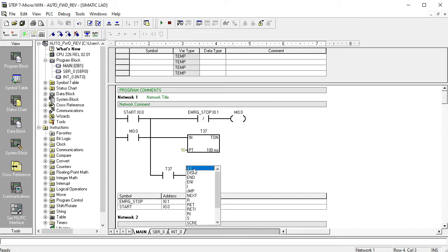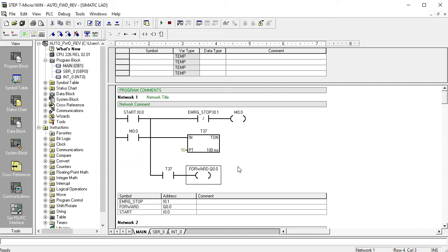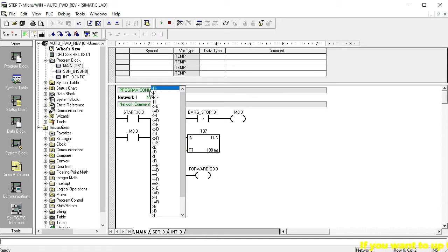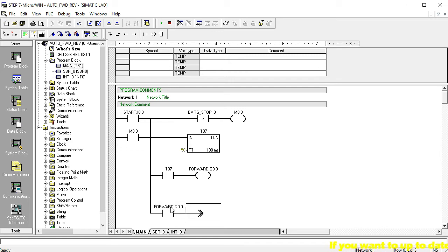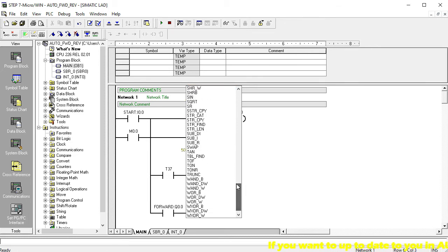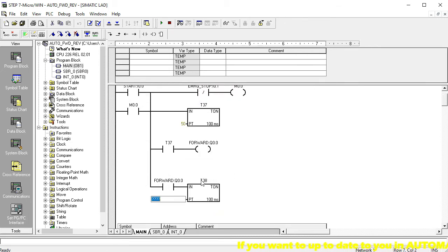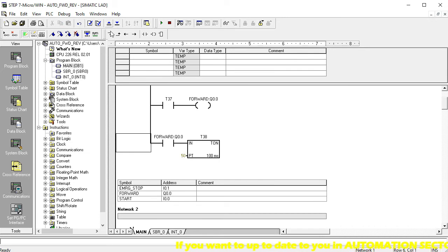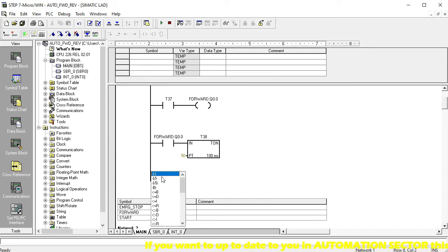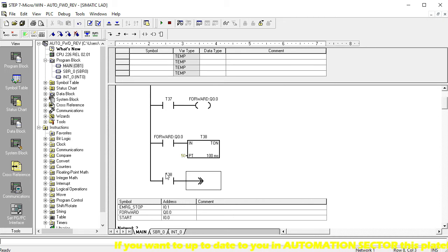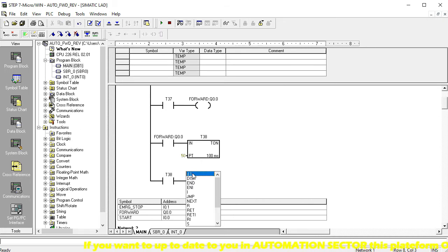Then go to the main output Forward — Q0.0. This is the tag writing facility: when you write your output, it automatically shows the make contact for Q0.0. Then add another TON timer T38 with preset 50 for another five-second delay. The make contact of T38 is used here, and then go to the second memory M0.1 — this is the second program memory relay.